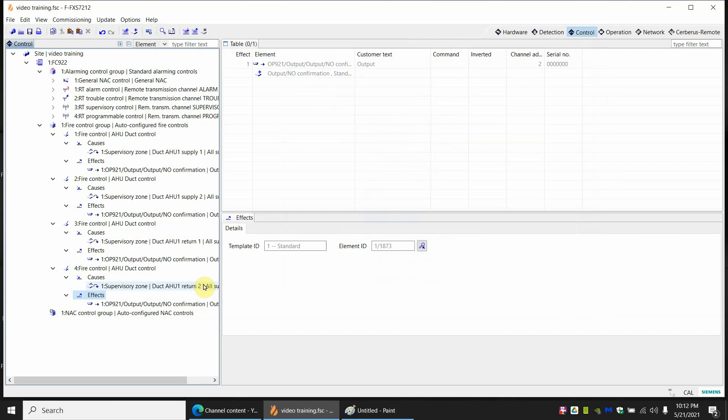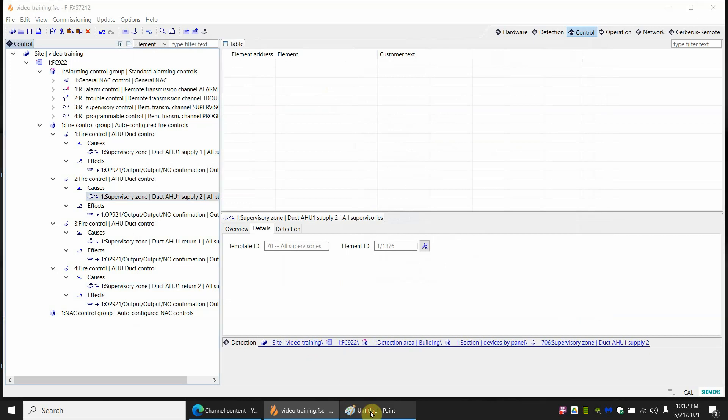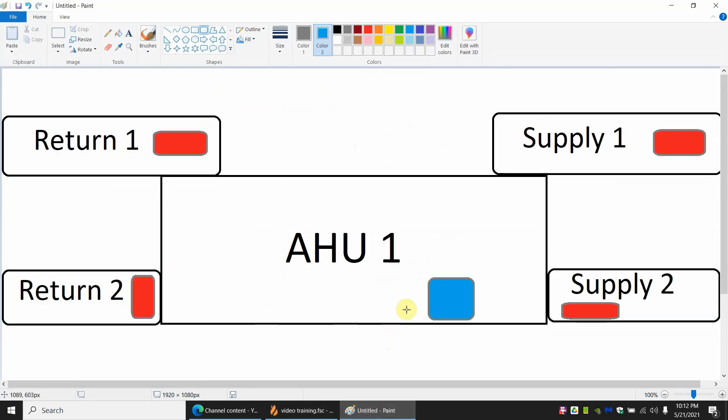Now if you can visualize, we have four controls. And we're saying for this duct detector, if this duct detector goes off, the relay associated with that duct detector will trigger. So if we run the wire to that, it will trigger that relay. This creates a scenario. And I drew a really crude picture here. Imagine we have a big air handler. We actually have these duct work coming in. We have two returns on the left side, two supplies on the right side. And I've seen some technicians, they would run a wire, a shutdown wire, to all four duct detectors, and then run it to the blue box, which would be the shutdown. So they would have to figure out relay logic to run it, to run one wire, that all four duct detectors, where if any one would trigger, it would shut down the unit. So first they have to figure out if it's normally open or normally closed connection for the shutdown. And then wire it to four relays. And then you're hoping that it's kind of clear to run between the four duct detectors.